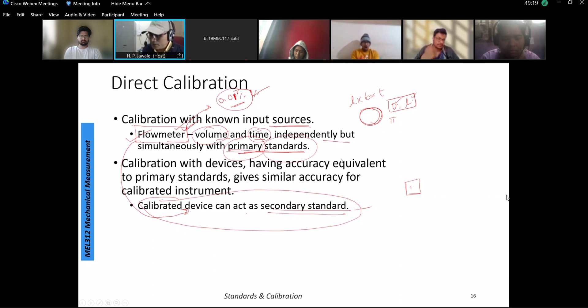Whereas indirect calibration is one where, suppose now this instrument is calibrated and I am using this instrument for measurement of this entity. So this is secondary because the calibrated device is used for measurement of the actual components. That is a secondary calibration. Whereas direct calibration, I am going to calibrate this by steel rule or a very preserved physical device for measurement of length. That is a direct calibration. I think this difference is clear to you. Direct calibration involves use of a primary standard as the main calibrating device or the main device for comparison. Whereas in secondary or indirect calibration, we use a calibrated device for knowing the accuracy of something else.